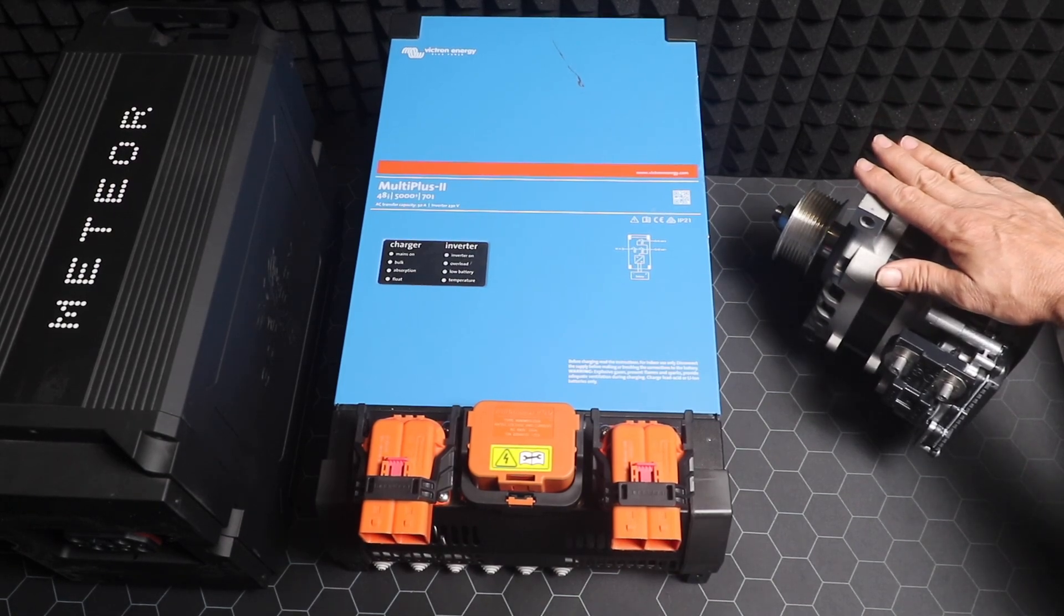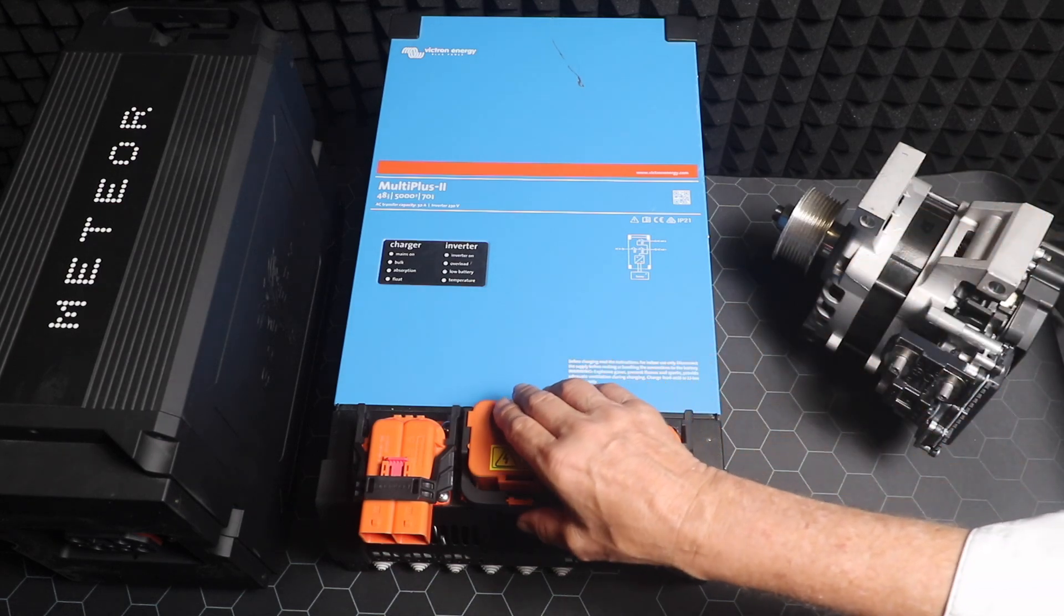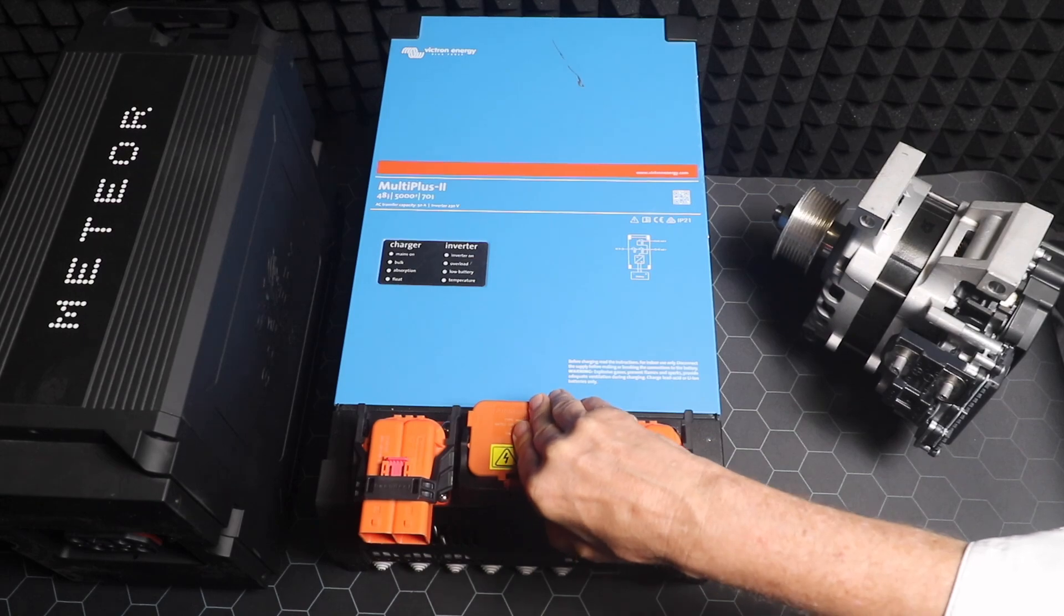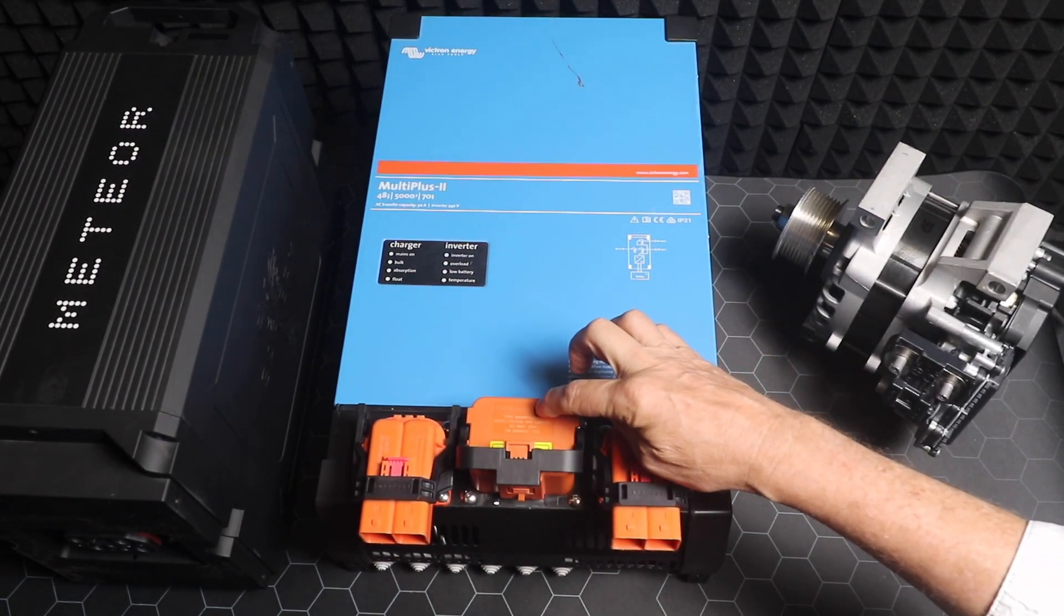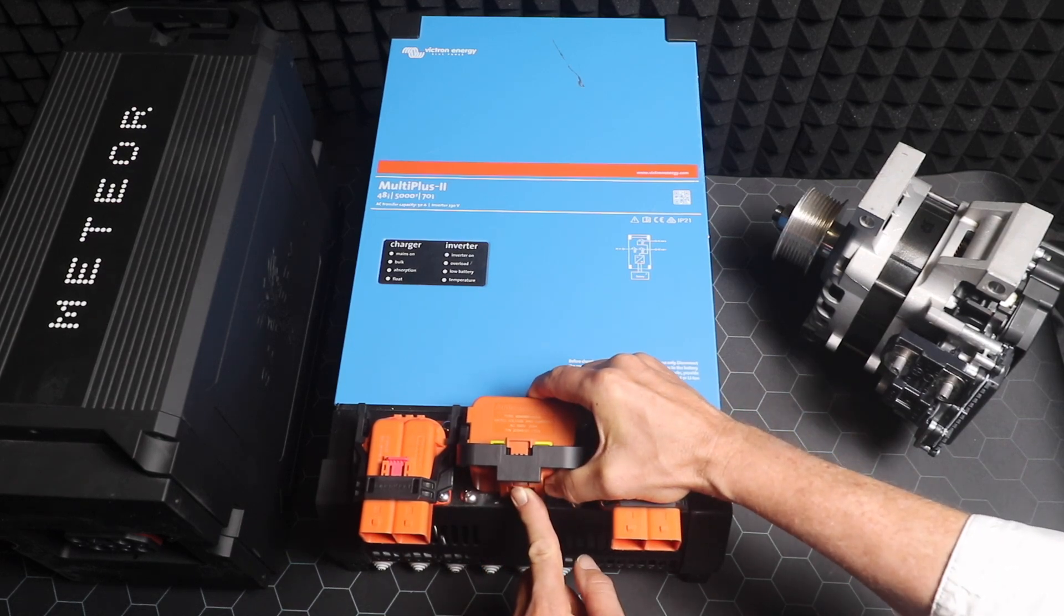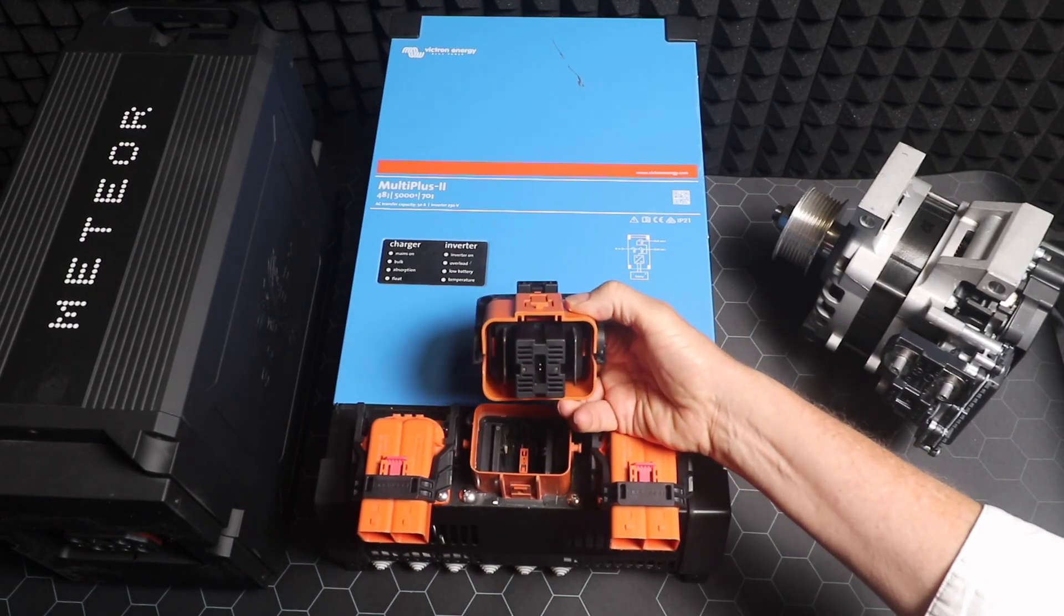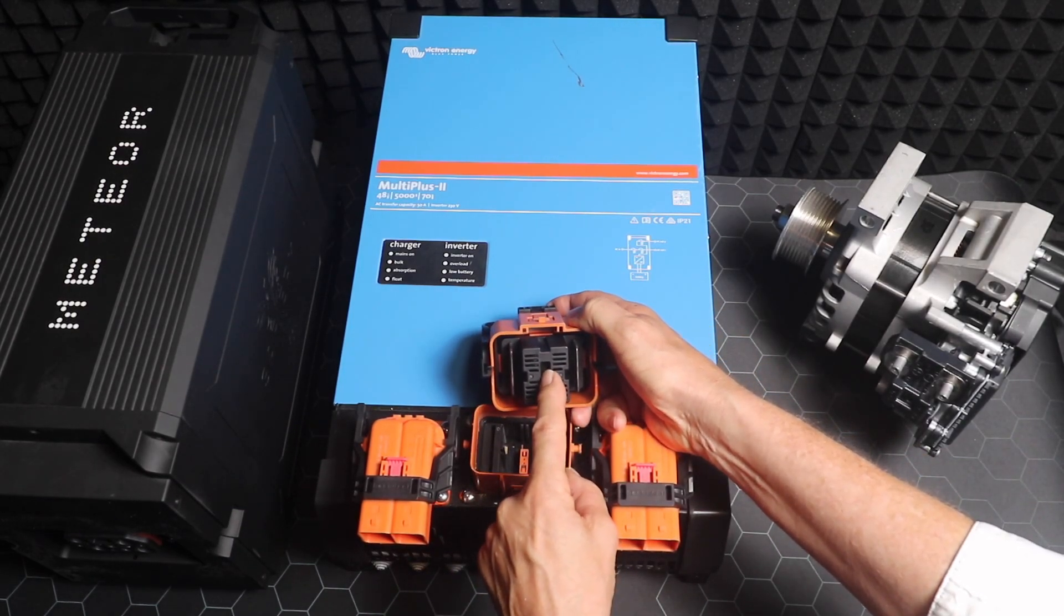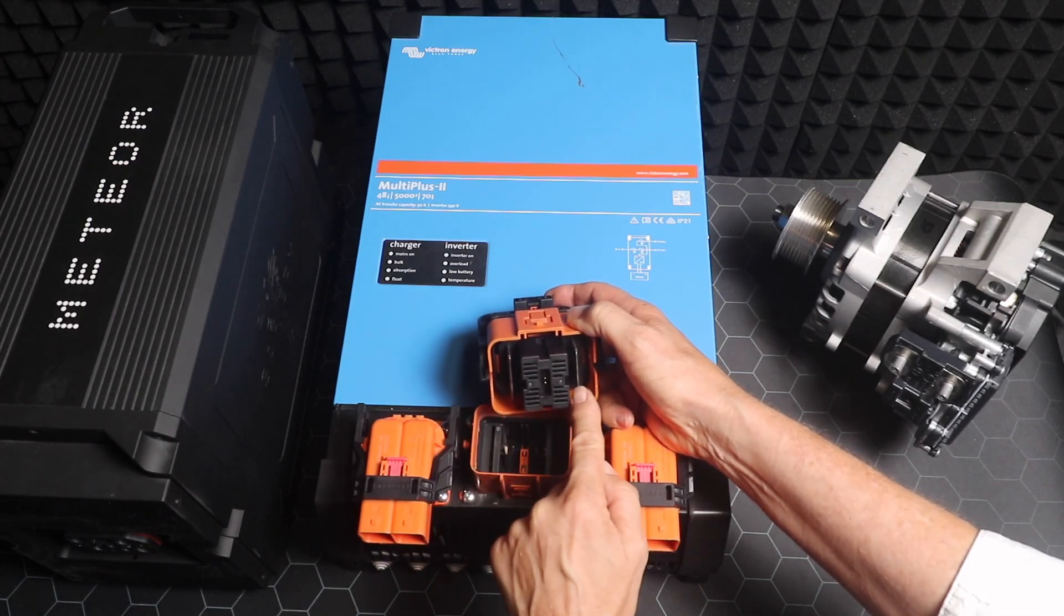Let's now have a look at how the interlock works. If I go and unclip this on the side, the protector, and lift it up to the first point, I can't pull it any further—the interlock is now disconnected. There's a little indent on the side here. I push that in, and as I push that in, I lift it out, open it up, and you should be able to see those two pins. They're the interlock pins that go into the bottom there, and then the blades on the side here.